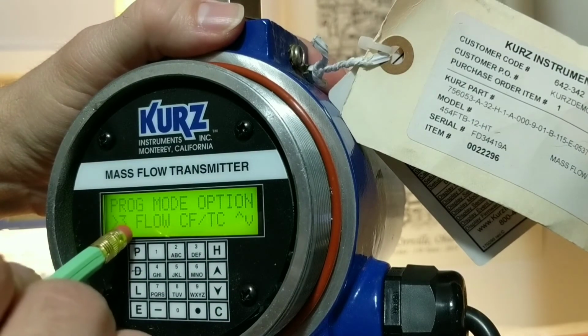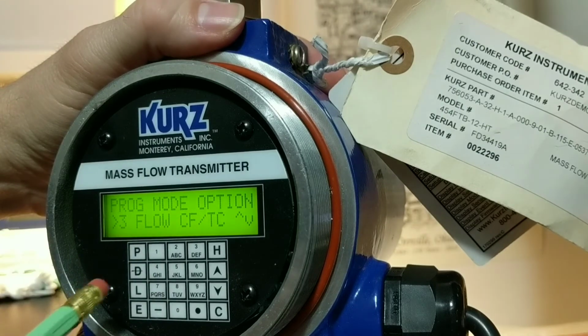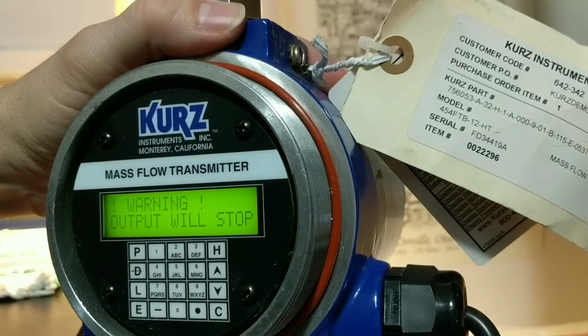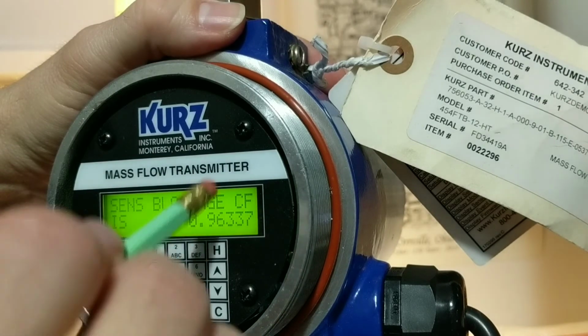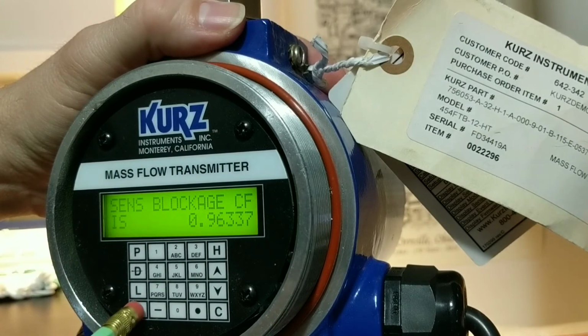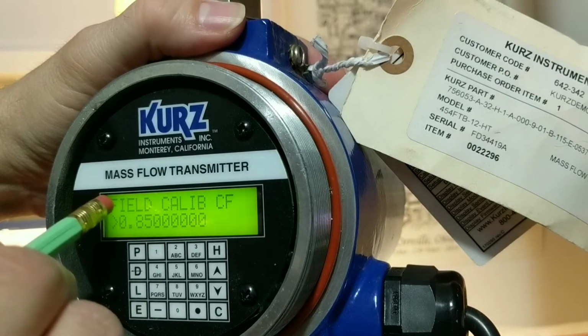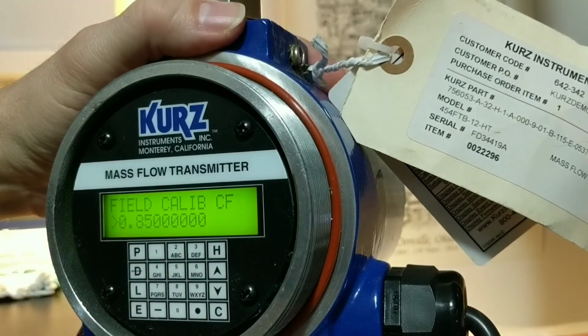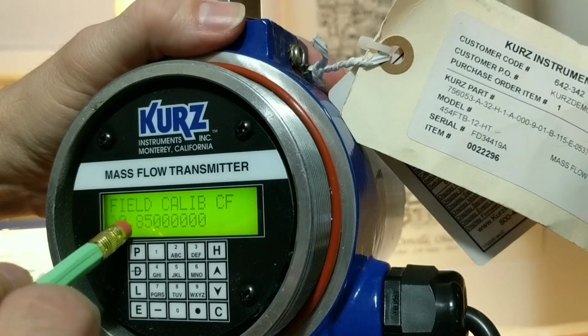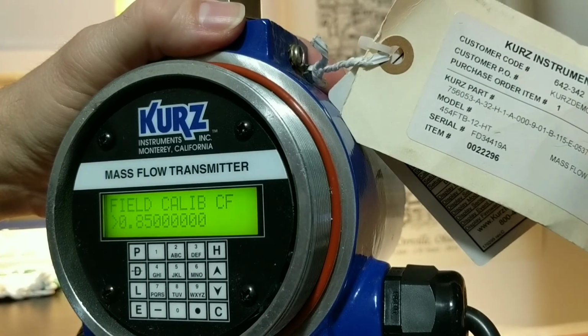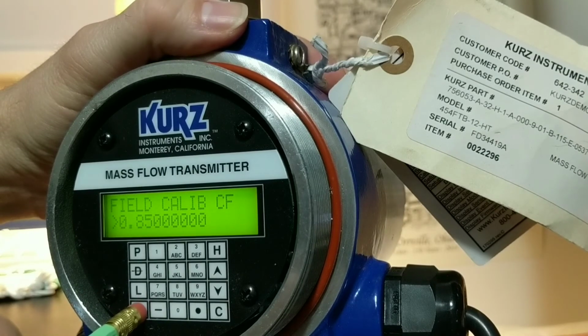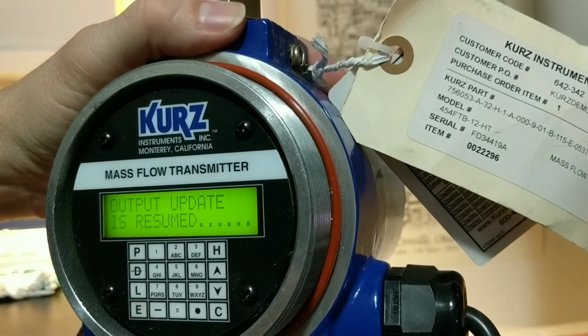And we're going to go to the flow correction factor. We need to double check that. So we're going to enter. Sensor blockage, don't mess with that. The field calibration correction factor should be set to 0.85. I don't think yours is set to 0.85, so you're going to clear that. You're going to put in the correct value, and then you're going to hit enter. And we're going to skip the rest of these.